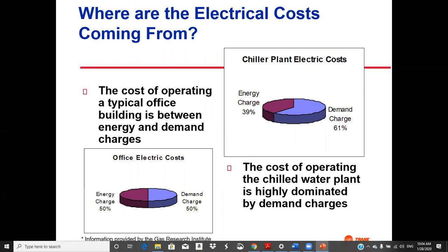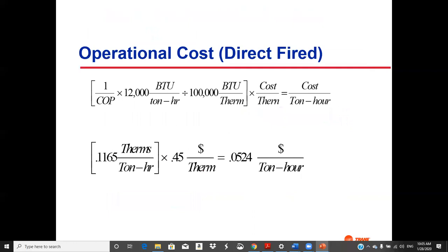Okay, this is kind of background information. Where are electrical costs coming from? The cost of operating a typical office building is kind of split. They're saying it splits about 50-50 between the demand charge and the energy charge, but the cost of operating a chilled water plant is highly dominated by demand charges. If you just segregate out the chiller plant, then you see 61% of the cost is tied up in demand and 39% is energy, because these things tend to have a high demand that sets that high peak.